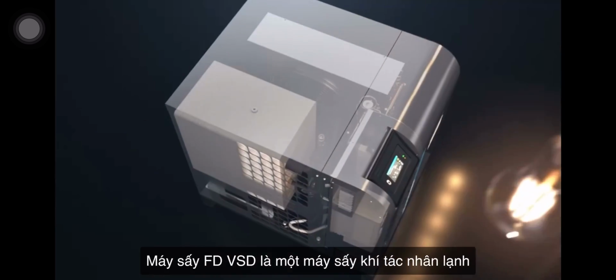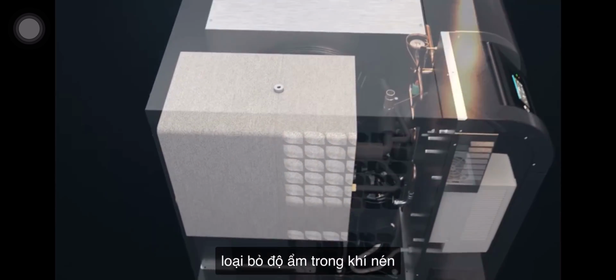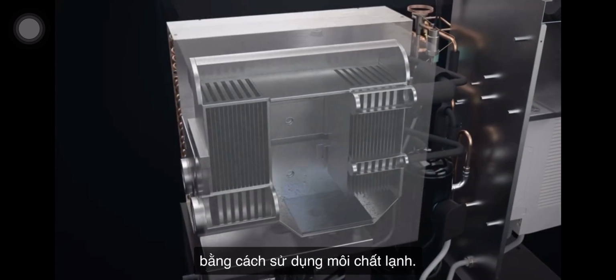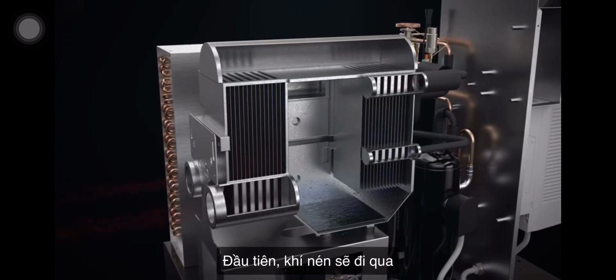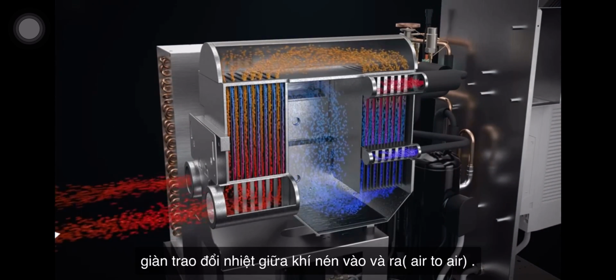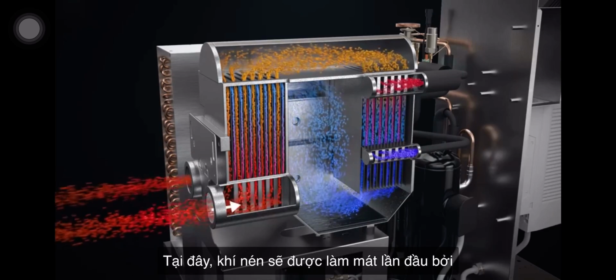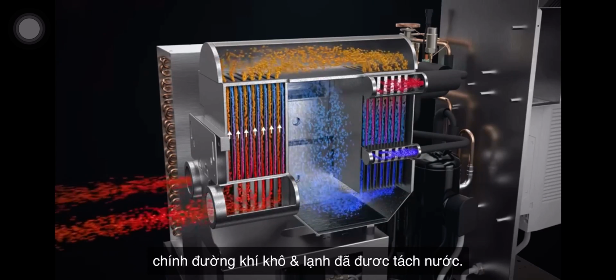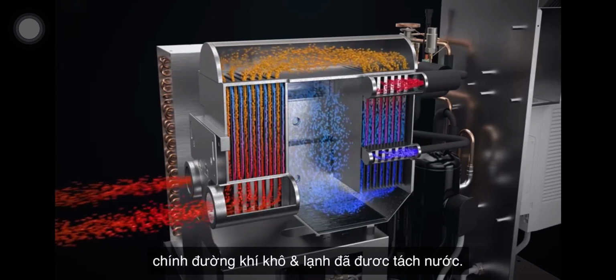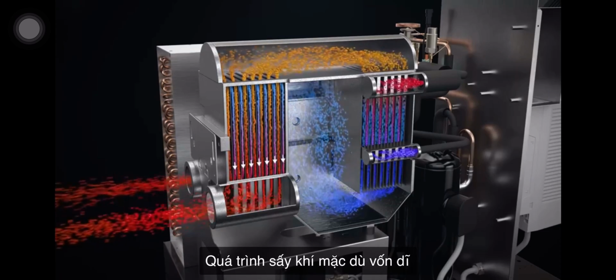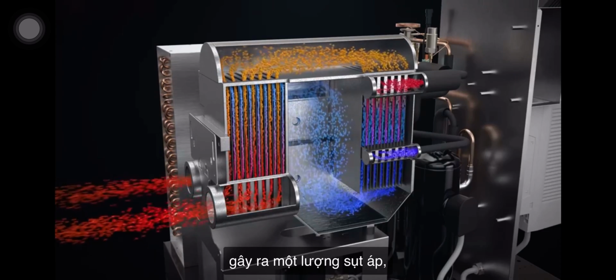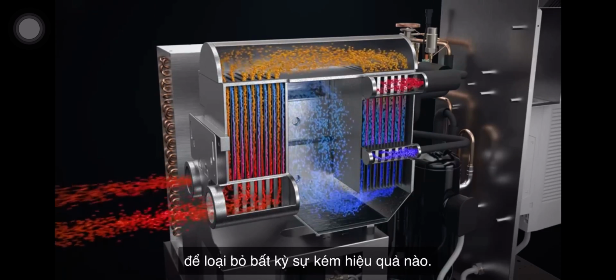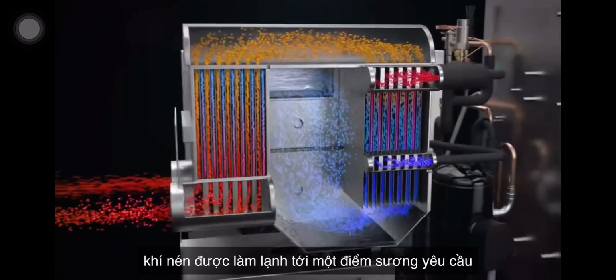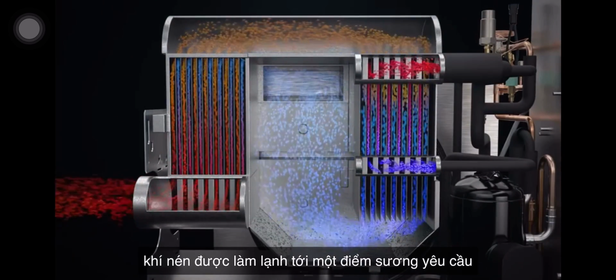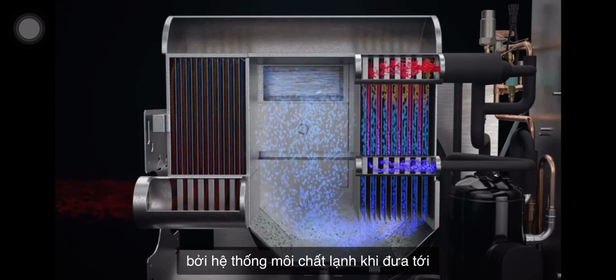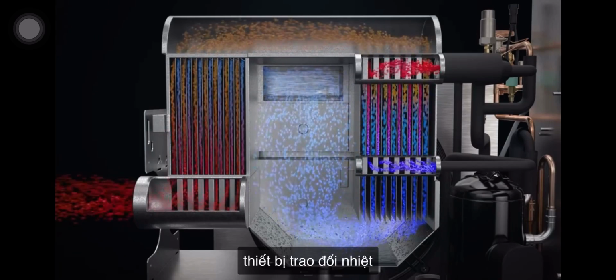The FD is a refrigerant dryer, which means it removes the humidity from compressed air by using a refrigerant gas. First, the incoming air passes through the air-to-air heat exchanger. Here it undergoes a first cooling by the dry, cold air that is leaving the dryer. Although this process inherently comes with a pressure drop, the FD was designed specifically to eliminate any inefficiencies. Next, the air is cooled to the required dew point by the refrigerant circuit in the air-to-refrigerant heat exchanger.